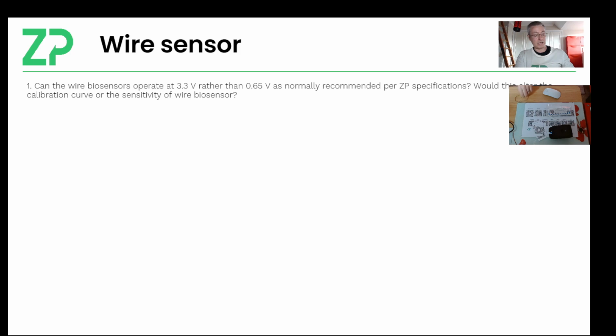650 millivolts is a good potential at which to oxidize hydrogen peroxide. If you use greater than that, you will end up doing the oxidation of hydrogen peroxide plus other molecules. Voltage, so rather potential in the units of voltage, is really energy. So the more energy you put into that system, the more molecules you can oxidize. So if you go higher than 0.65 volts, then you will start co-oxidizing other molecules. Once you start getting towards 1 volt, you'll start doing electrolysis of water. So 3.3 volts is disastrous. You'll get lots of current and lots of gas bubbles, and you're really doing electrolysis of water. And the answer to your question is, you can't really run these biosensors at 3.3 volts. You'll put lots of current through them.